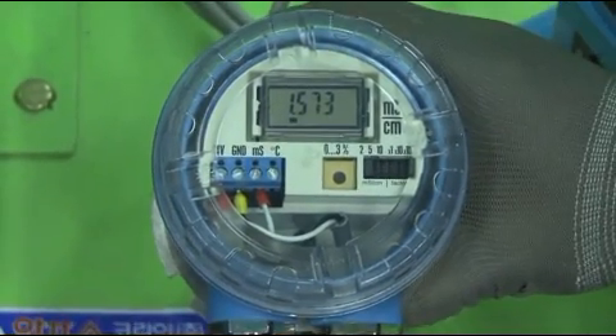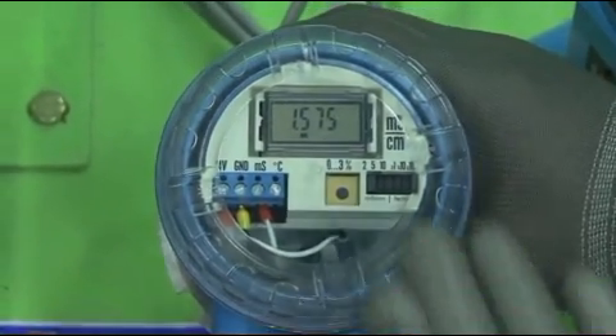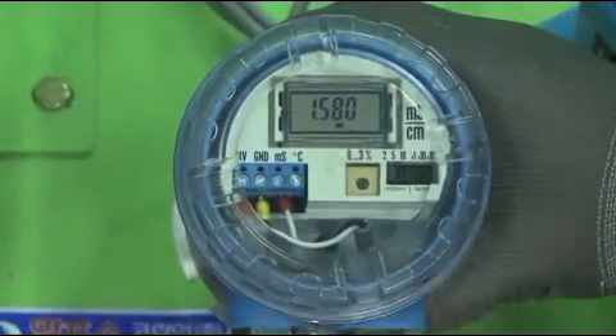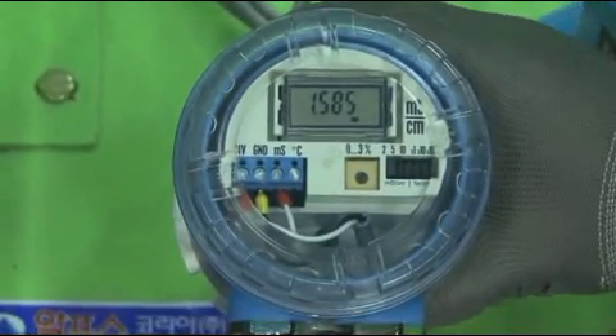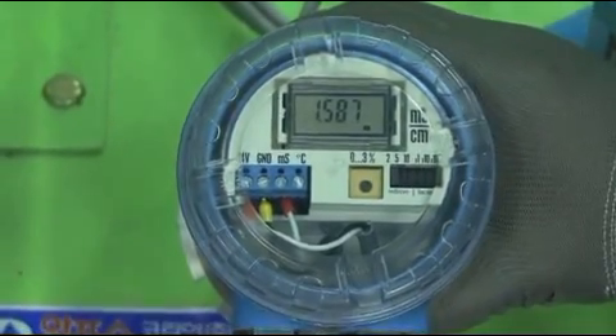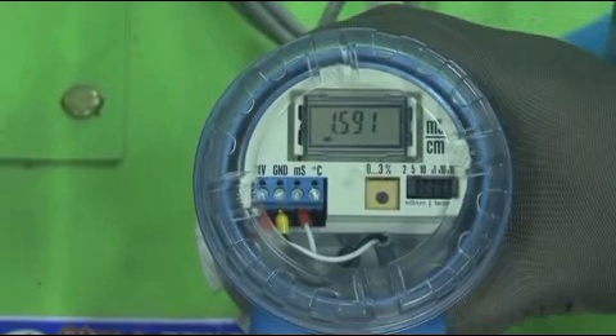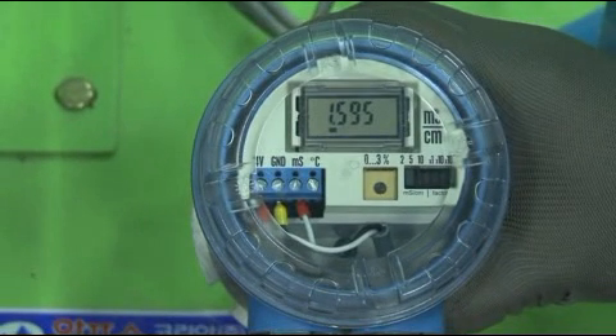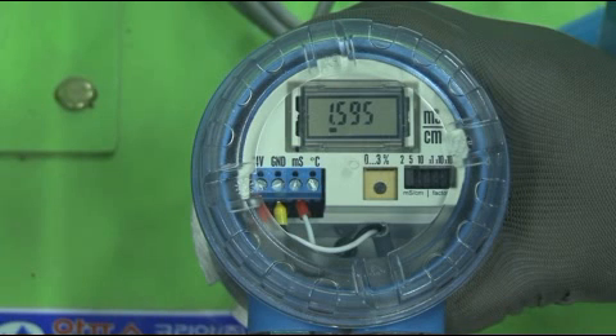If ECS operates outside the range of the salinity from 0.1 to 4.2%, it is not possible to produce normal TRO concentrations. If CSU displays the value lower than 1.7 milliSiemens per centimeter, ECS may not operate properly. There are exceptions in case control valve for conductivity concentration is supplied as an option.